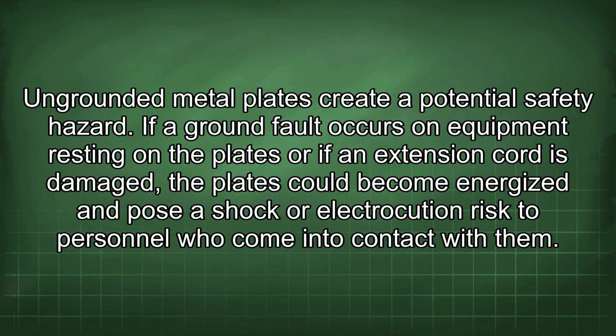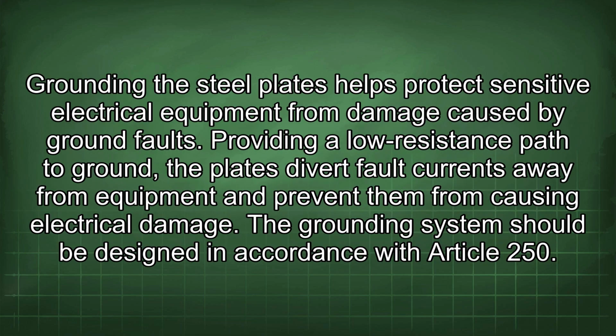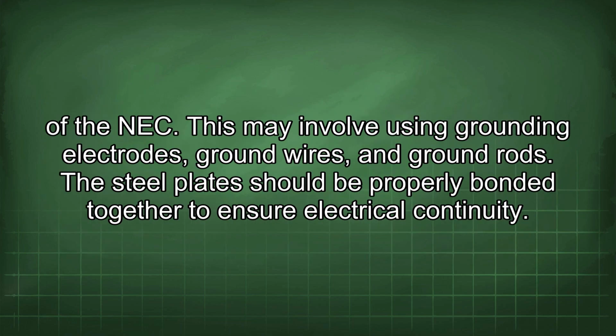If a ground fault occurs on equipment resting on the plates, or if an extension cord is damaged, the plates could become energized and pose a shock or electrocution risk to personnel who come into contact with them. Grounding the steel plates helps protect sensitive electrical equipment from damage caused by ground faults. Providing a low resistance path to ground, the plates divert fault currents away from equipment and prevent them from causing electrical damage. The grounding system should be designed in accordance with Article 250 of the NEC.